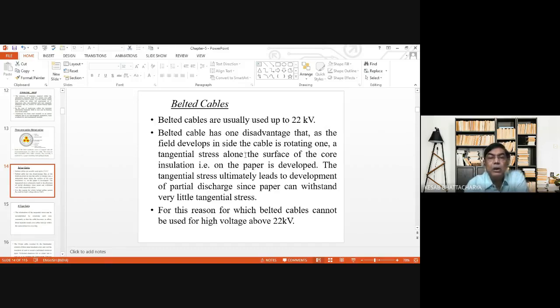Along the surface of the core of the insulation, that is on the paper, tangential stress is developed due to the rotational electric field. It has been found that paper cannot withstand high tangential stress, and if used beyond 22 kV, the magnitude of the rotating field and resulting tangential stress is so much that it leads to failure of such cables.